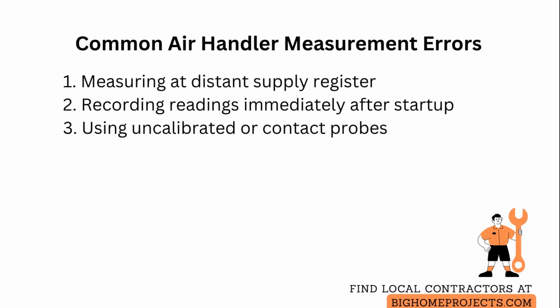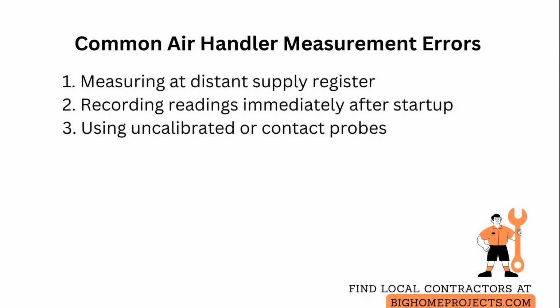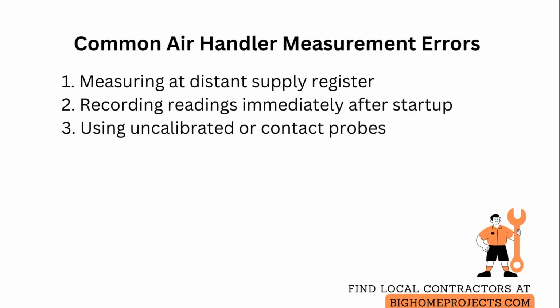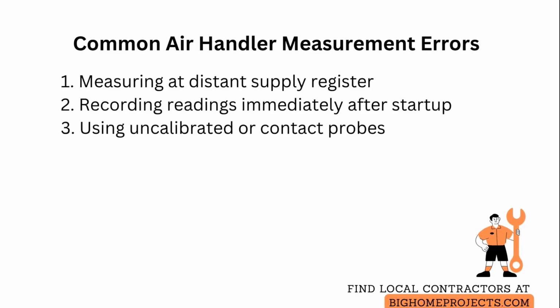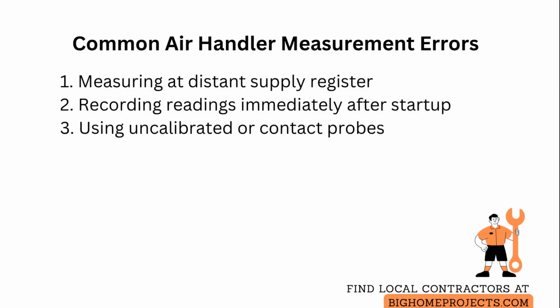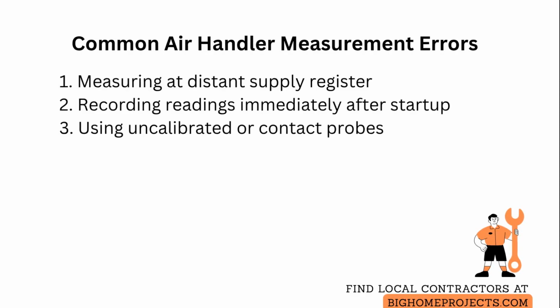A third problem is using a thermometer that is not properly calibrated or placing the probe against the register face, which warms or cools the sensor. So use a calibrated instrument and suspend the probe in the airstream without contact.